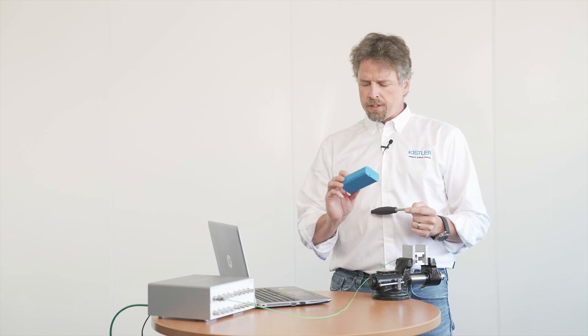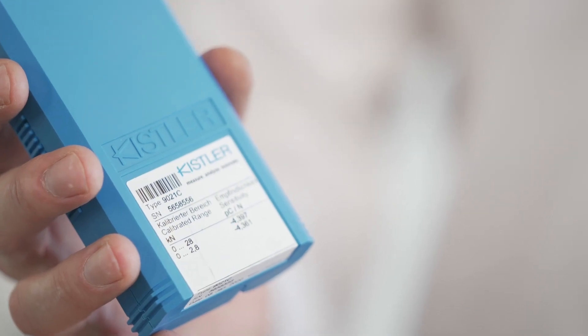The important here is you set up the right sensitivity. You find it here on the sticker of your sensor. It is the full range which is mentioned here.